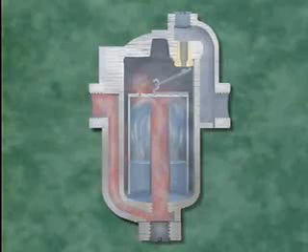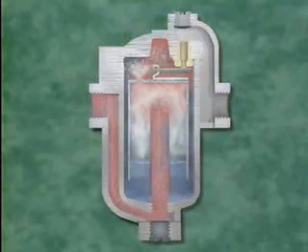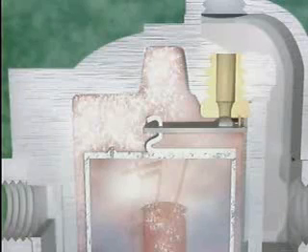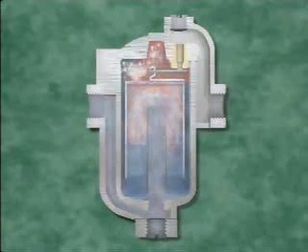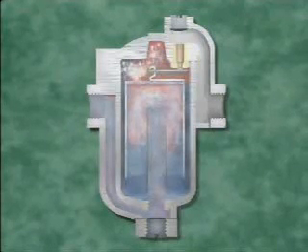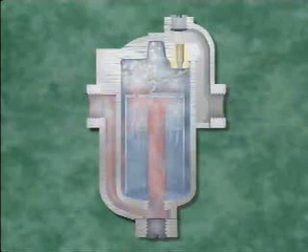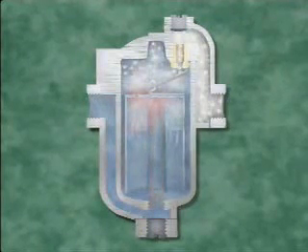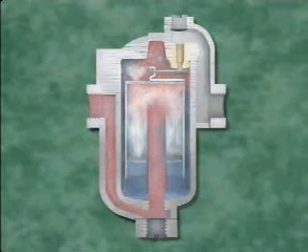When steam enters and accumulates to fill about two-thirds of the bucket, the bucket floats and the trap valve closes, so no more condensate discharges. While the valve remains closed, air and non-condensable gases, which are less dense than the condensate, pass through the bucket's vent and collect in the cap area of the casing. More condensate then enters the bucket and some of the steam condenses. When only about a third of the bucket's volume is filled with steam, the bucket drops and the trap valve opens. Accumulated air is discharged first, then condensate. The flow of condensate under the bottom of the bucket picks up dirt and sweeps it out of the trap. Condensate continues to discharge until more steam floats the bucket and the cycle repeats.